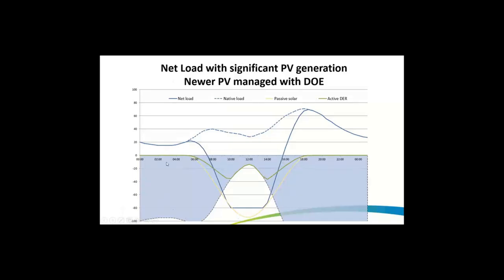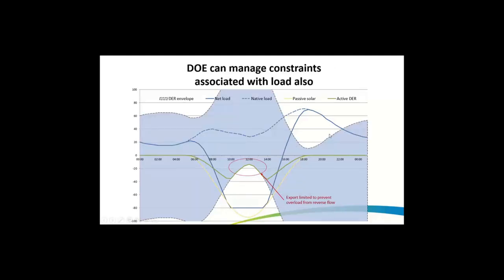During most of the day, there is plenty of capacity for the new PV systems to inject into the distribution network. But during the middle of the day, when there's excessive reverse flows, the dynamic operating envelope limits the reverse flow so that the system capacity constraints are not breached. Dynamic operating envelopes can also be used to limit the flexible loads on the system, such as electric vehicles that charge. And so when the network is particularly heavily loaded, this can reduce the charging from any EVs, for example.